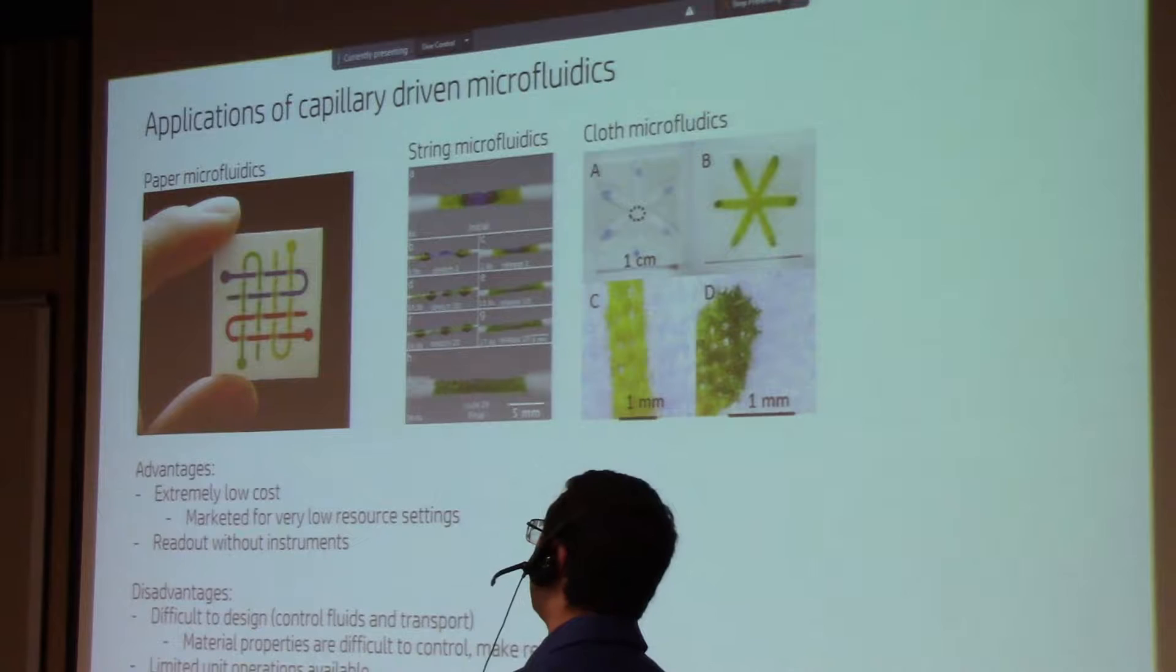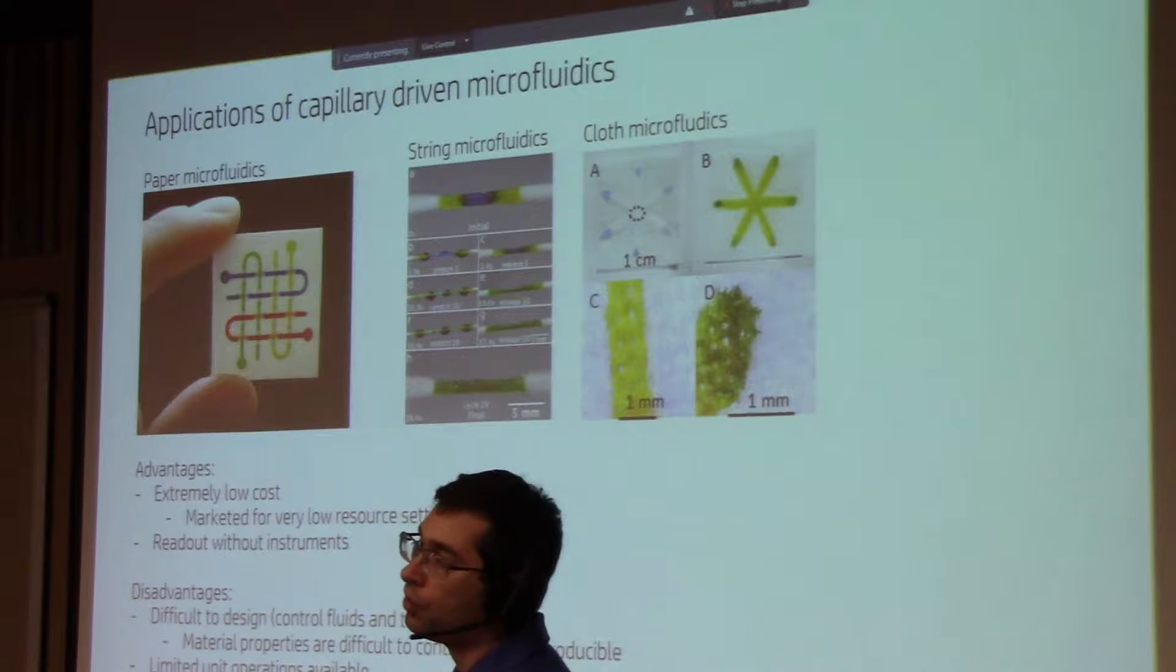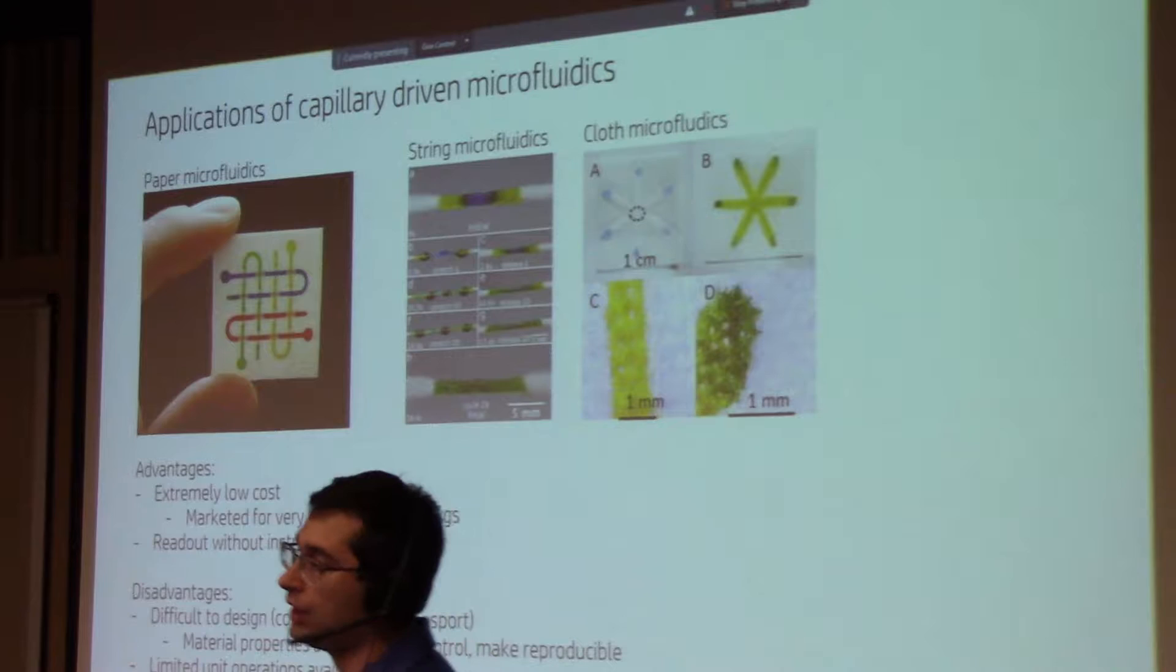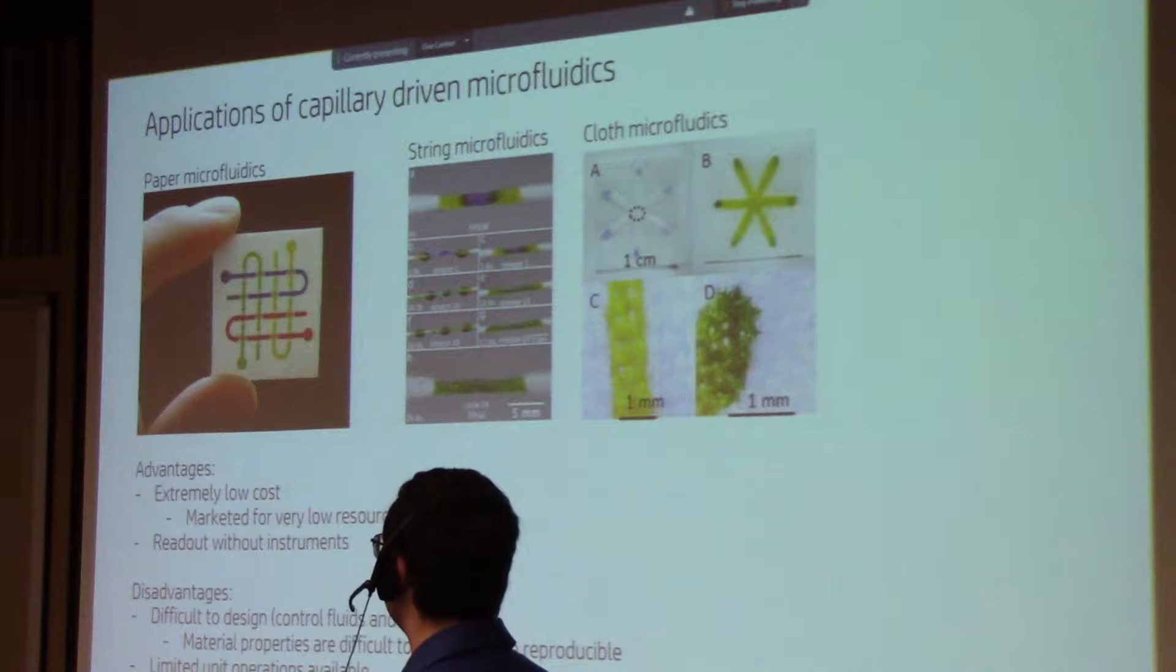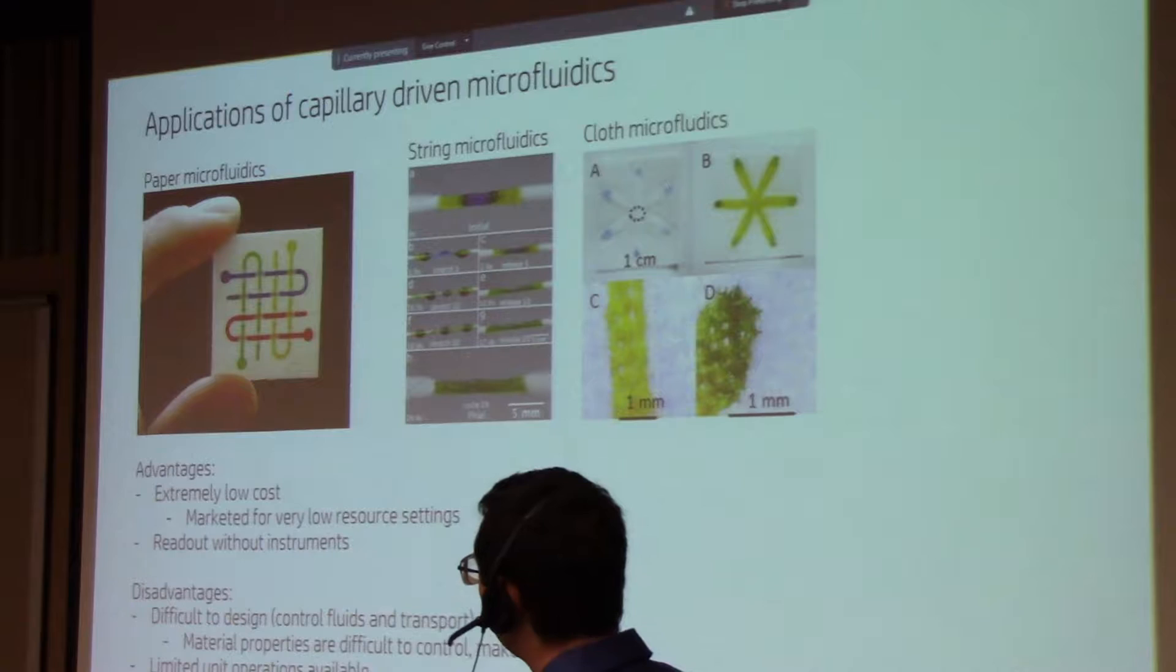However, there are significant disadvantages to these as well. They are fairly difficult to design because you rely on the surface properties of this paper. These surface properties often change. The surface properties of the sample or the wetting properties of the sample changes, maybe because of the disease state that the patient is in or the sample that you are trying to detect is in. And they make this fairly difficult to reproduce. So your flow rates might be different from run to run. You have to keep that into account.